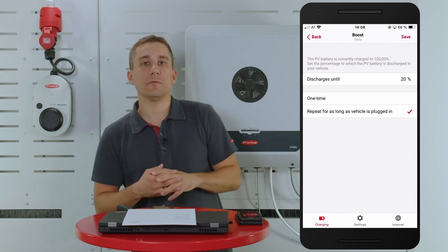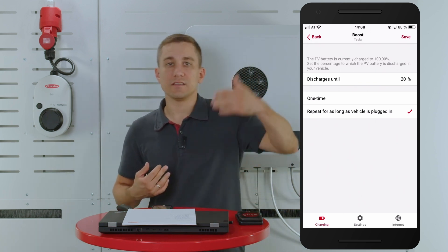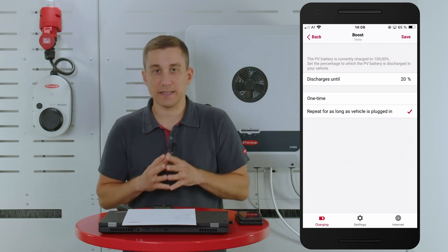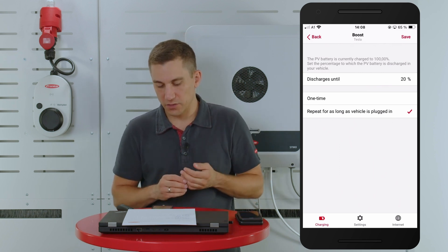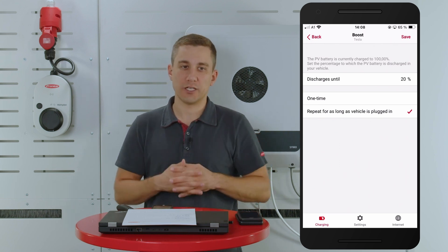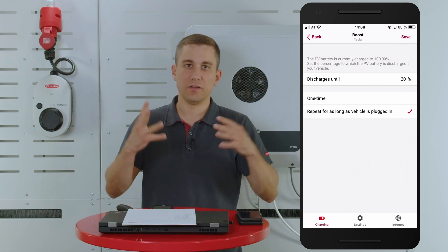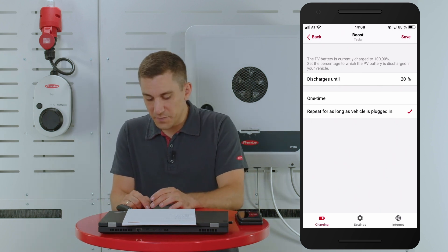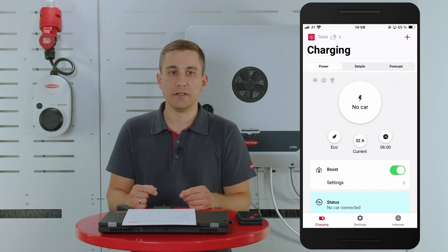Please also note that there is a threshold of 5% to prevent the electric vehicle from repeatedly starting and stopping during the charging process. This means the PV system will wait until the battery threshold of the stationary system reaches 25% in our case, and then it will restart the charging process. This prevents an on-off behavior. When you have done the settings, please hit the save button — this is really important so that the Wattpilot will apply the new behavior.